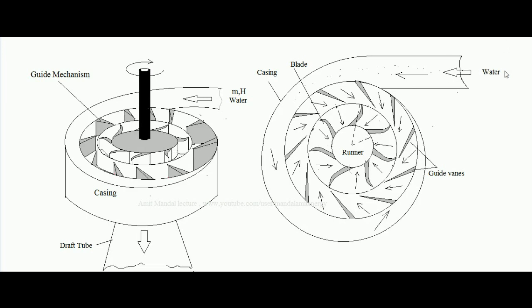Water comes from the water source — generally a dam — by the help of a penstock. At the end of the penstock there is a spiral casing, which is the first part of the Francis turbine. Water passes through the casing toward the guide mechanism, which consists of blades implanted at a particular angle to direct water toward the center of the machine.